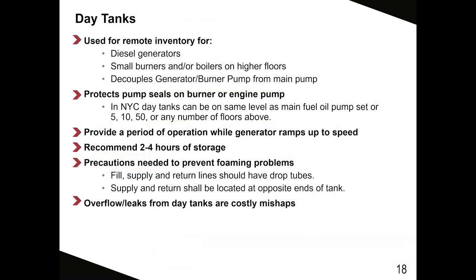Day tanks. Day tanks are used for emergency generators, boilers, and other fuel burning devices. They provide a remote limited supply at the fuel burning device and decouple the appliance pump from the main transfer pump on the bottom floor. We recommend 2 to 4 hour storage at the remote device. Use drop tubes to prevent foaming problems. The return pipe can be extended at least half the distance to the bottom of the tank.